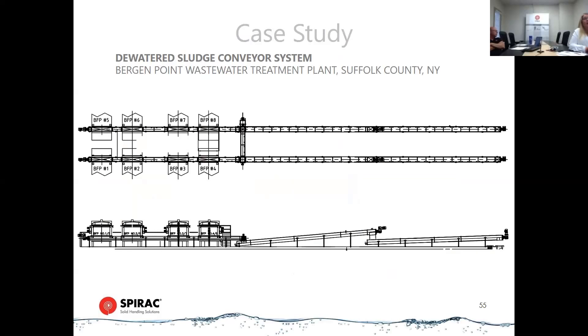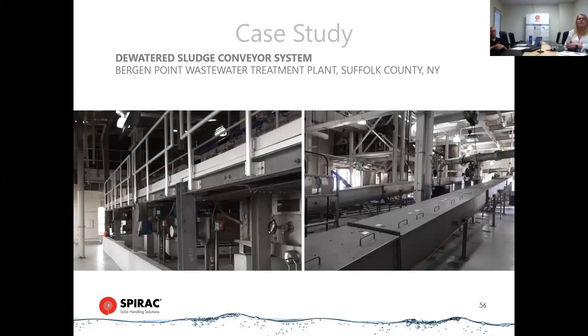One more case study: Bergen Point. These are all 75-foot long U-620s — a U-trough — and they have quite a few belt filter presses feeding into it with dual trains. In the middle is a cross conveyor that goes from one side to the other depending on what trucks they want to load. They had originally had some other conveyors that were not sized properly, so SPIRAC was able to come in and offer a solution that helped them. They're very happy — they've been running for seven to eight years, and it's been a good installation.